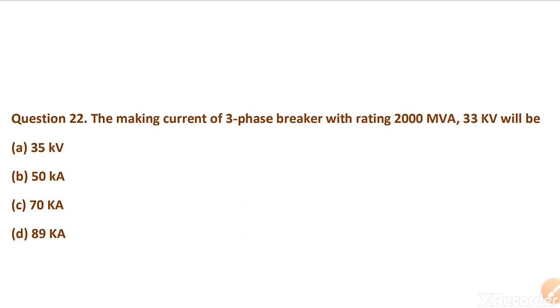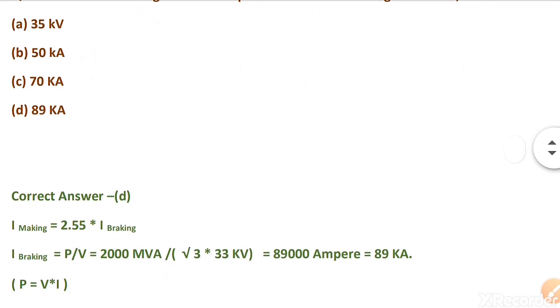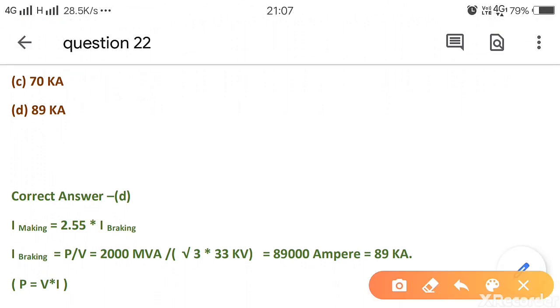The making current of a three-phase breaker with a rating of 2000 MVA at 33 kV will be calculated as follows. Making current is equal to 2.55 times the breaking current, and breaking current is equal to P divided by V — that is, the MVA rating divided by the voltage.